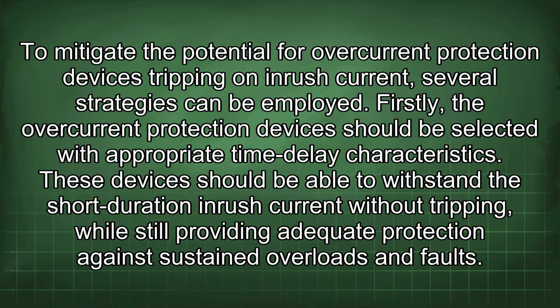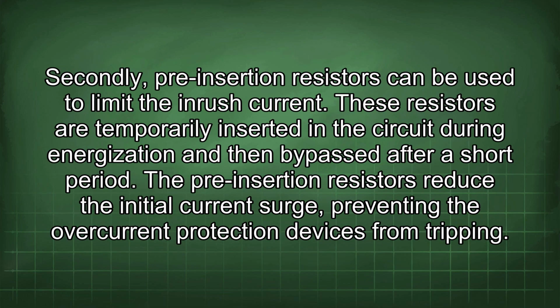To mitigate the potential for overcurrent protection devices tripping on inrush current, several strategies can be employed. Firstly, the overcurrent protection devices should be selected with appropriate time delay characteristics. These devices should be able to withstand the short duration inrush current without tripping, while still providing adequate protection against sustained overloads and faults. Secondly, pre-insertion resistors can be used to limit the inrush current. These resistors are temporarily inserted in the circuit during energization and then bypassed after a short period. The pre-insertion resistors reduce the initial current surge, preventing the overcurrent protection devices from tripping.